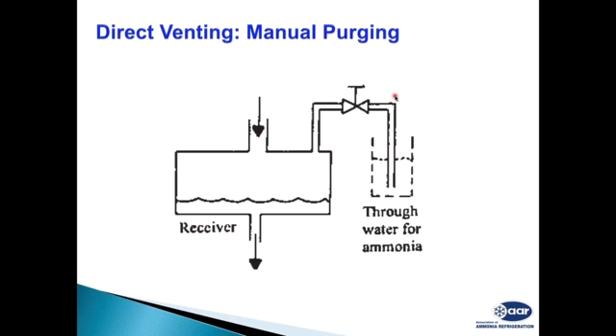and then open the valve manually. One has to take the most important precautions when opening these valves. You should wear the mask, the gloves, the goggles, so that in case ammonia comes out of this valve, you are not affected. And third, the possibility of ammonia leakage is always there. These precautions are very important.